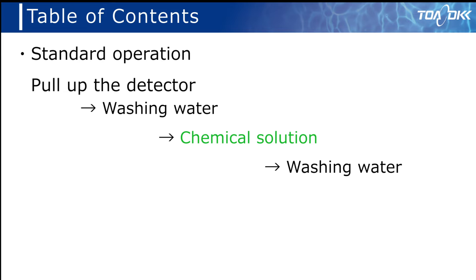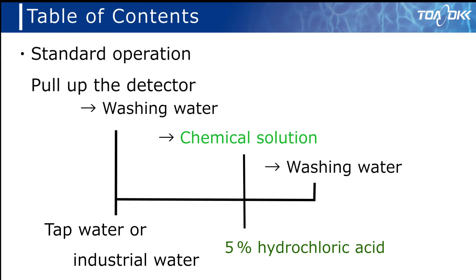The standard operation is to pull up the detector and wash in the order of wash water, to chemical solution, and to wash water. Use tap water or industrial water for cleaning water, and 5% hydrochloric acid for chemicals.